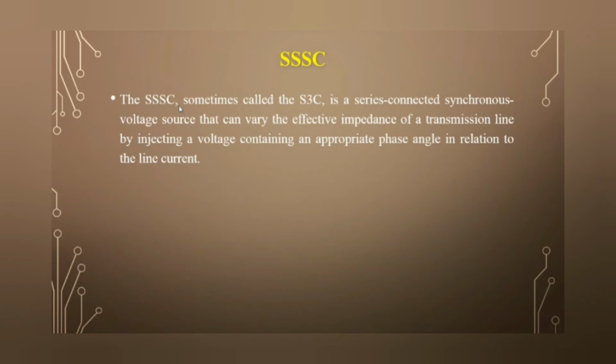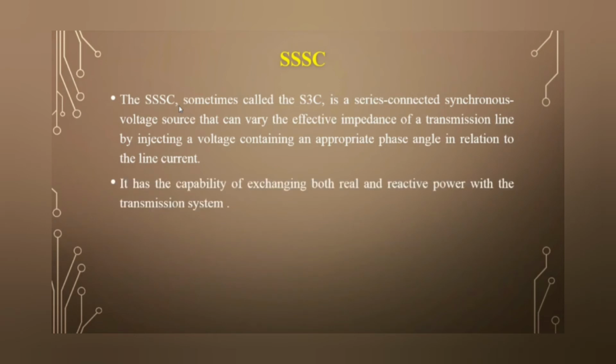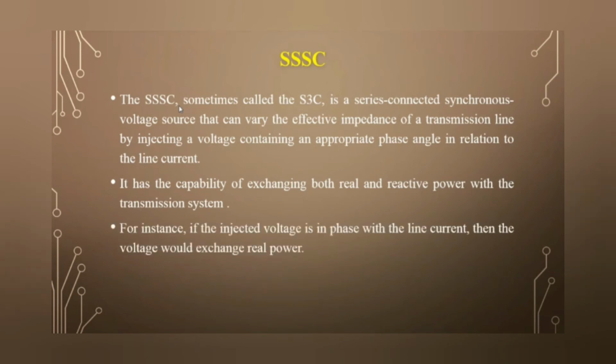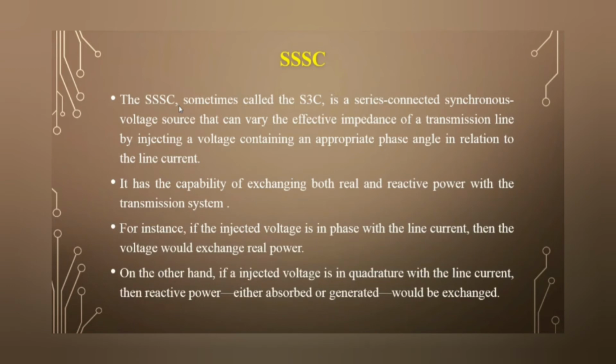It has the capability of exchanging both real and reactive power with the transmission system. If the injected voltage is in phase with the line current, then the SSSC voltage would exchange real power. And if the injected voltage is in quadrature with the line current, then reactive power, either absorbed or generated, would be exchanged.